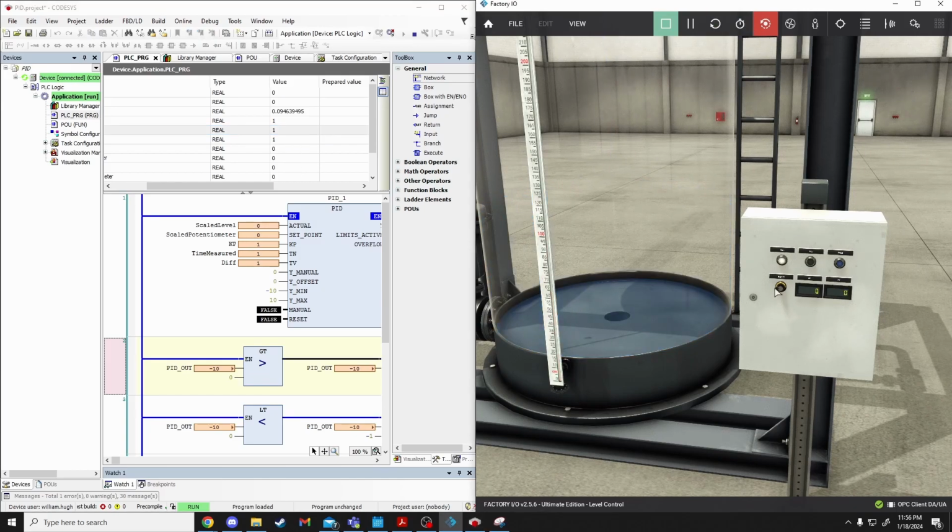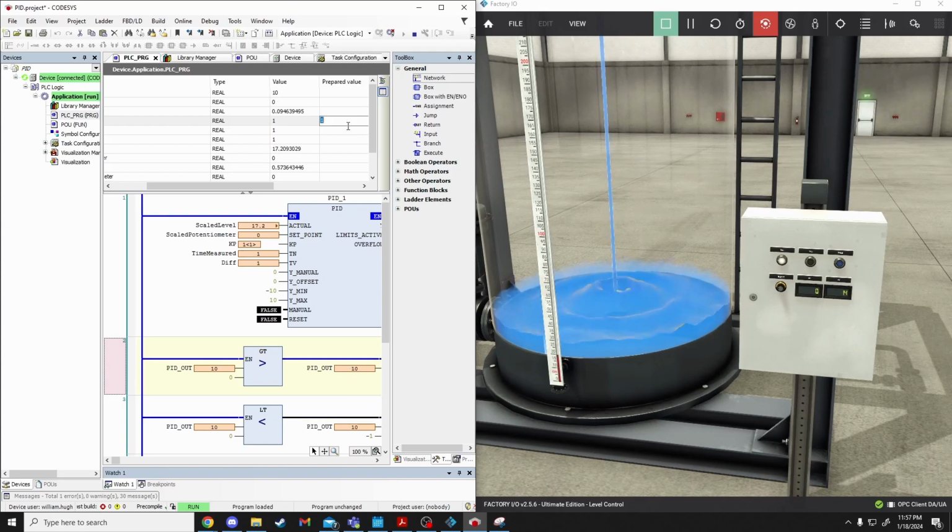Let's hit reset on that. The values I have that worked, I'll go ahead and plug those in for demonstration. Typically, when you're tuning PIDs, what you would do though is you would start with 0 integral and 0 derivative, and you would just start with your K value. There's a whole process for PID tuning. I think I'll maybe link that rather than making this video any longer.